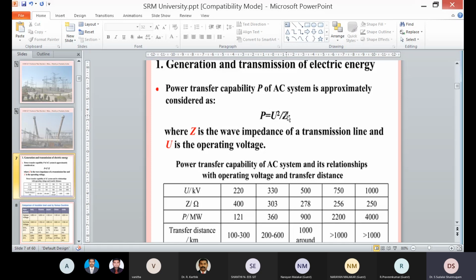You can just see P is equal to U square by Z. Z is the surge impedance of the line. Z is equal to root of L by C. Again, L by C is a function of the transmission conductor. So P is equal to U square by Z. If I substitute, U is 220 kV and Z is 400, the power will be around 120 megawatt. That is 121, which I have shown here. This is the common nomenclature we are following in India as well as elsewhere in the world. I have not shown 1200 kV because we are still studying that. It is not commissioned for commercial purpose.